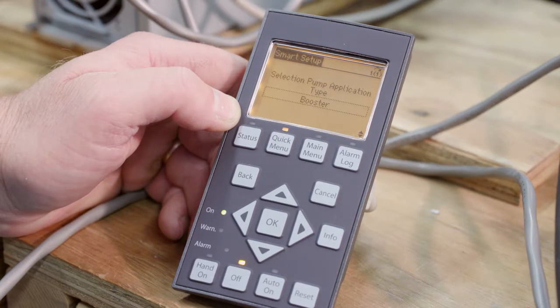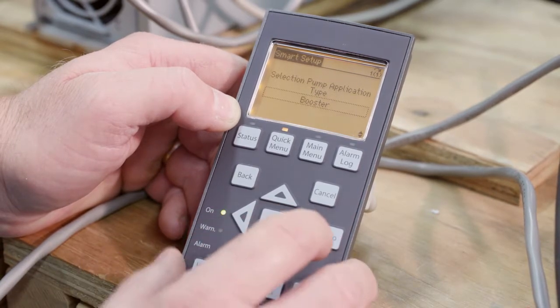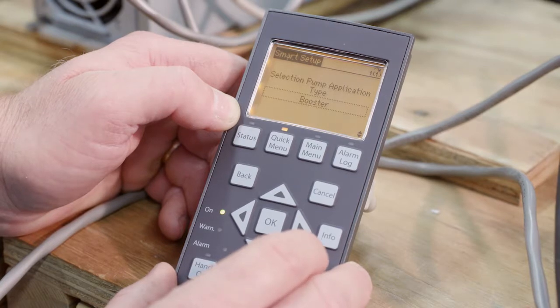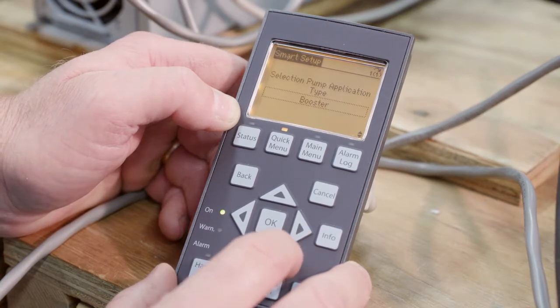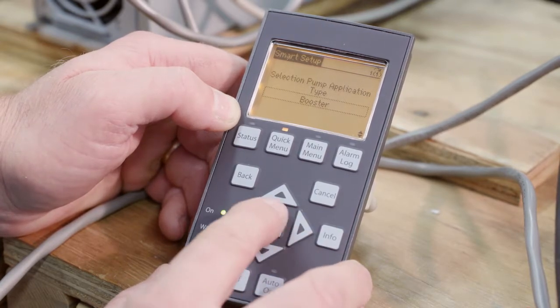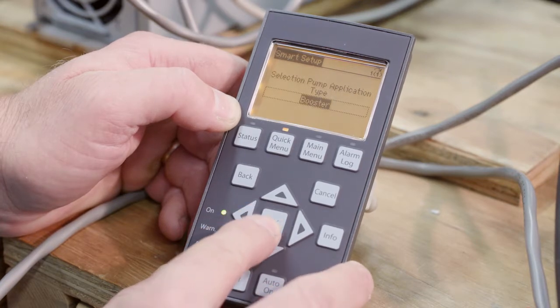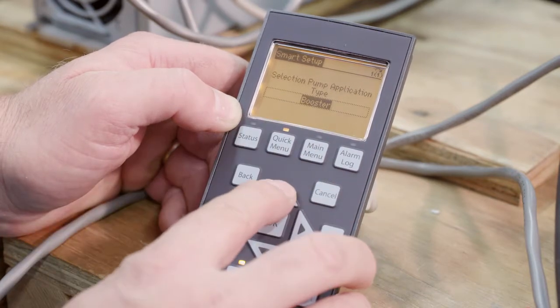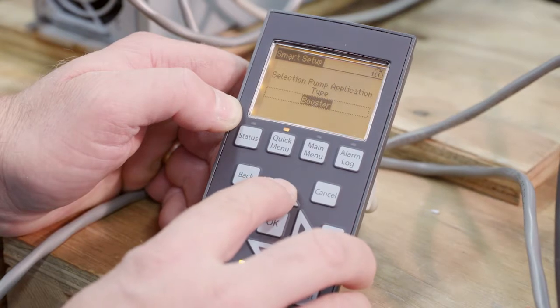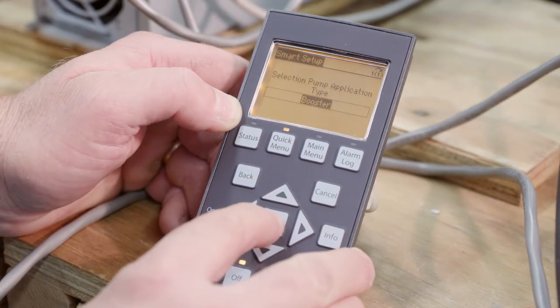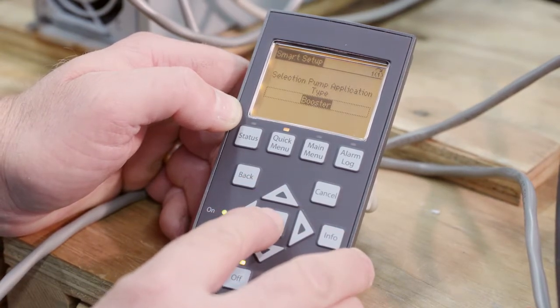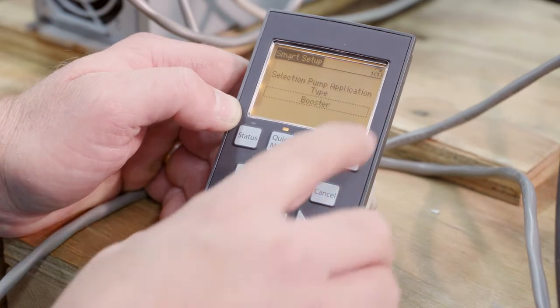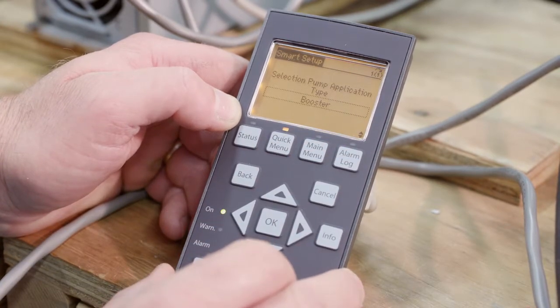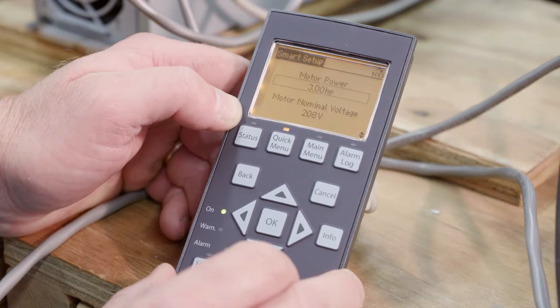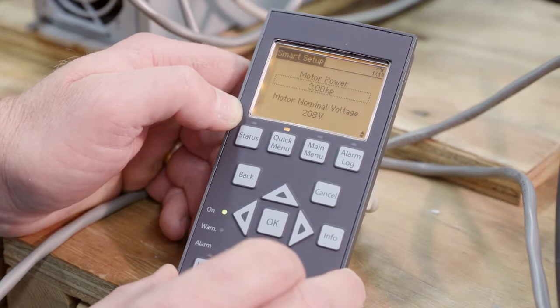Pump type application: booster. Yes, this is a booster application. If you ever wanted to see some different options, you would press the OK to highlight it, and you would see whatever option you have. So this is a booster. We're pumping from tanks and boosting pressure. So again, hit the down arrow to save. Now you have to set up your motor information.